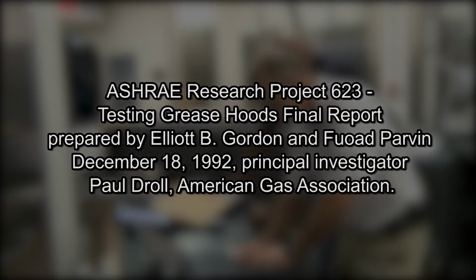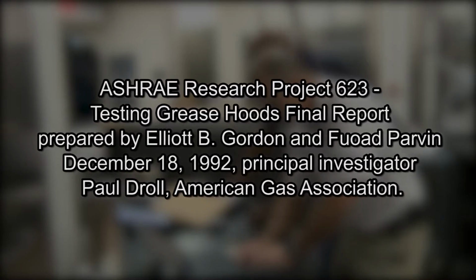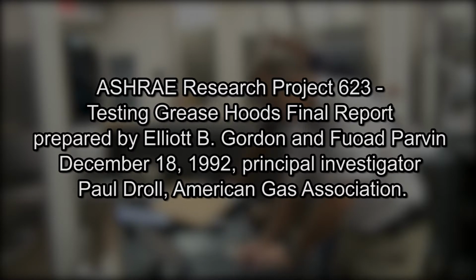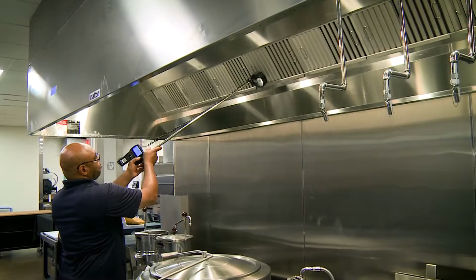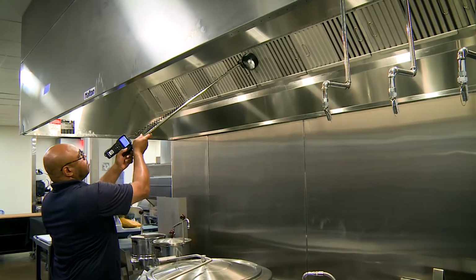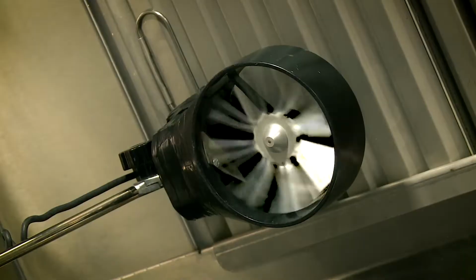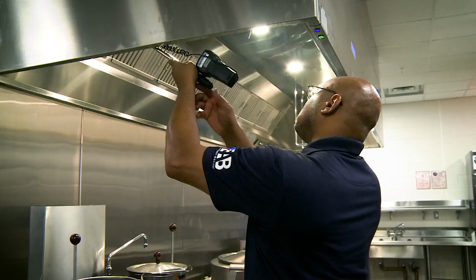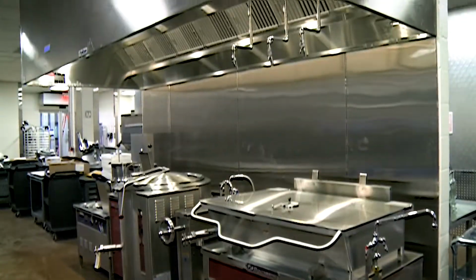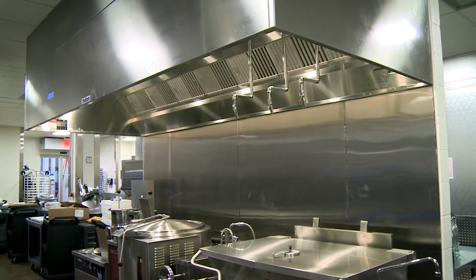Gordon and Fuad Parvin, December 18, 1992. Principal Investigator Paul Droll, American Gas Association. The grease hood test was developed to establish airflow of a grease hood with a rotating vane anemometer because there was no other method. The method can be used on any hood with grease filters.